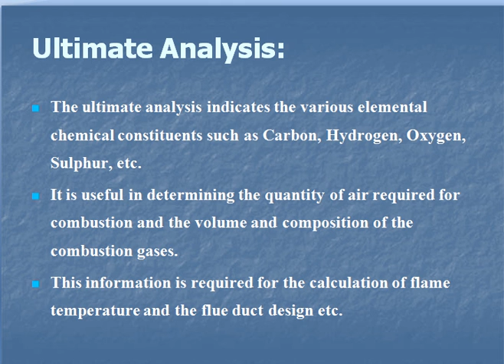However, ultimate analysis we can expand to include the entire element profile, because coal is found under the earth's surface, so most elements will be found in trace amounts. But the must-do analyses in ultimate analysis are percentage carbon, percentage hydrogen, percentage oxygen, percentage sulfur, percentage nitrogen, and percentage ash. This is required for calculation of flame temperature, flue duct design, and calculation of the quantity of air required for combustion, all these. It is very important.